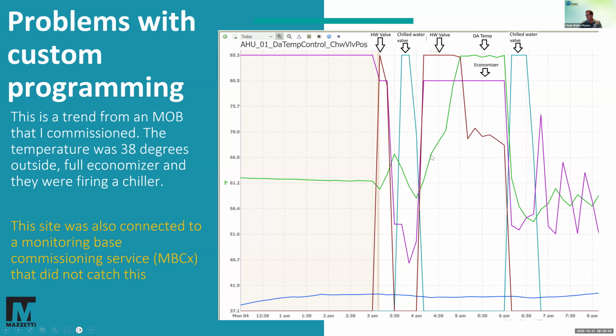Then you see the discharge air temperature coming up in reaction to the hot water valve. It figures out it's where it needs to be, drops those, opens the chilled water valve again, which restarts the chiller, and then drops that again. Then it finds some kind of stable control. This is called a hunt, by the way, when it's trying to find itself using just the economizer. You've lost from 3 a.m. to about 7 a.m. before it figured out where it was. You've lost a lot of energy and probably did more harm than good.